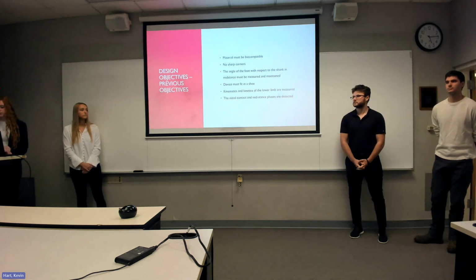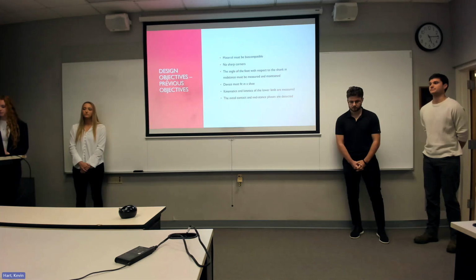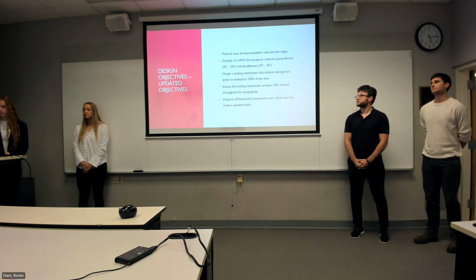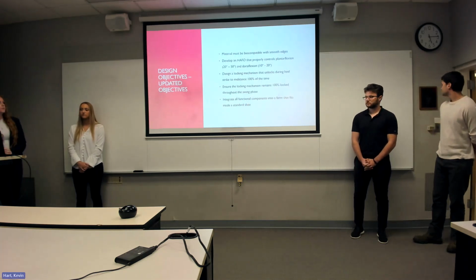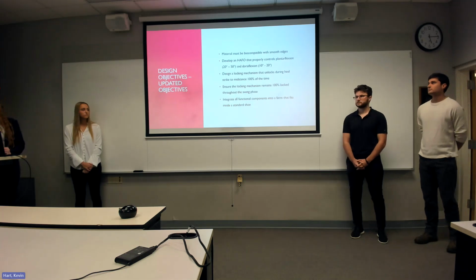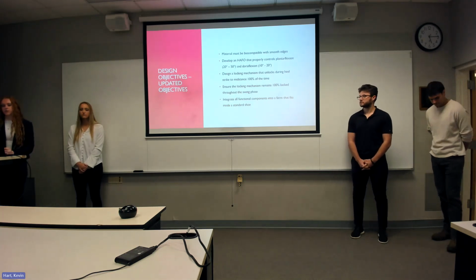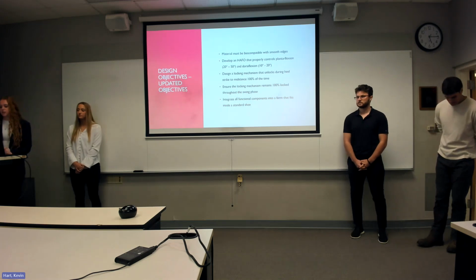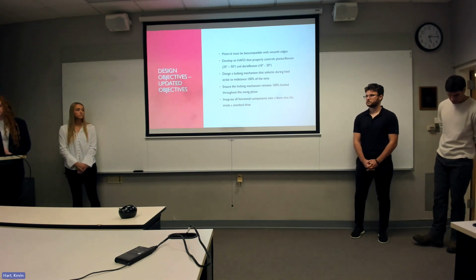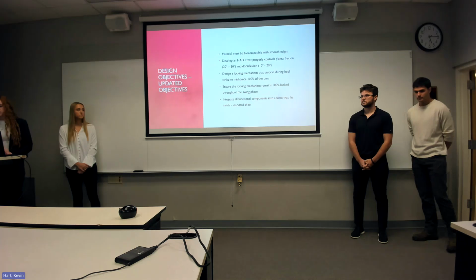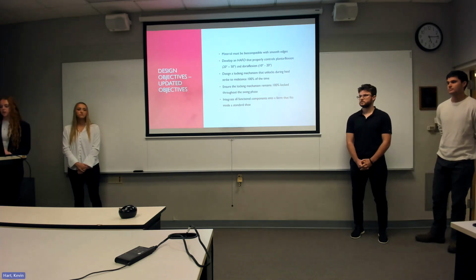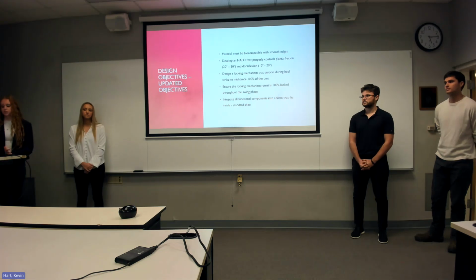Because of that, our team refined the objectives to focus the device on what it physically does, not just what can be measured. We kept the core safety requirements such as biocompatible materials and smooth edges, as these are non-negotiables when it comes to a medical device. The biggest change is that we shifted from measuring motion to actively controlling motion. So our goal is now to reliably control plantar flexion and dorsiflexion, which directly addresses the foot drop issue.